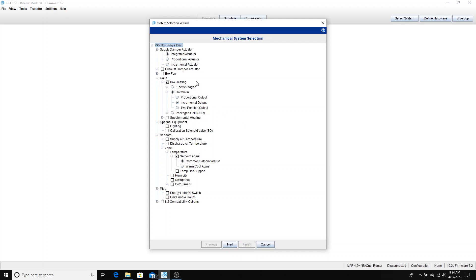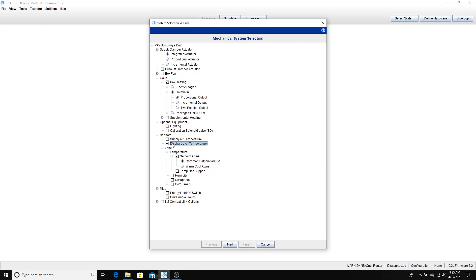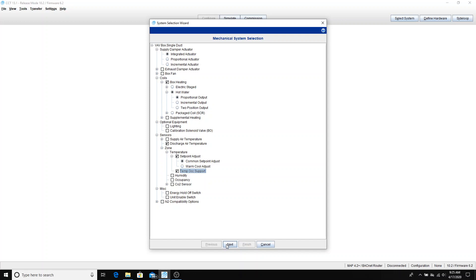We're going to be using a PCV 1630, which has an integrated actuator for the supply damper. We're going to say that it has a coil. It's going to be a reheat coil, so we'll say it's a hot water coil, and I'm going to use a proportional output as opposed to an incremental output. So proportional output would be a 0 to 10 volt output. We're going to move our way down. I'm going to put a discharge air temperature sensor on there so I can tell if my hot water coil is working or not. I'm going to use a temperature sensor with a set point adjust, the common set point adjust, as opposed to warm cool adjust. And I'm going to include temporary occupancy support.